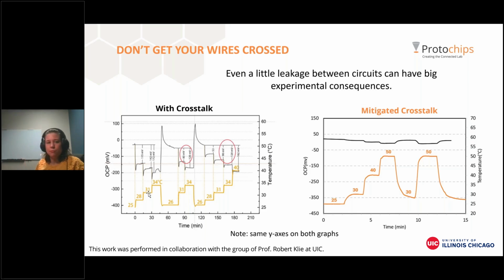We have to have multiple circuits. We have to have 2 different channels. One is going to control the heating and measure the temperature, and one is for electrochemistry. But you need to be very, very careful to make sure that you're mitigating the amount of leakage between those 2 circuits. And this is because we're looking at stuff on the nanoscale, right? Which means we're looking at nanoamps, picoamp levels of reaction currents and things like that.